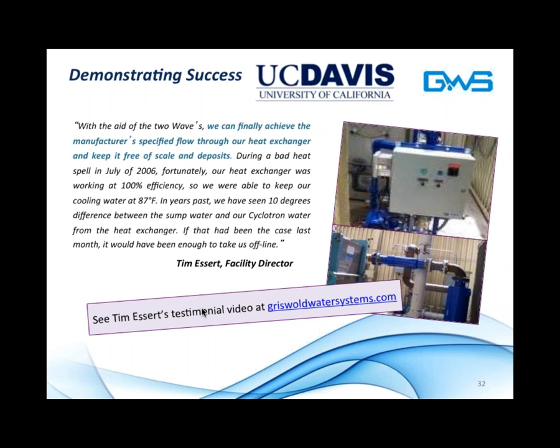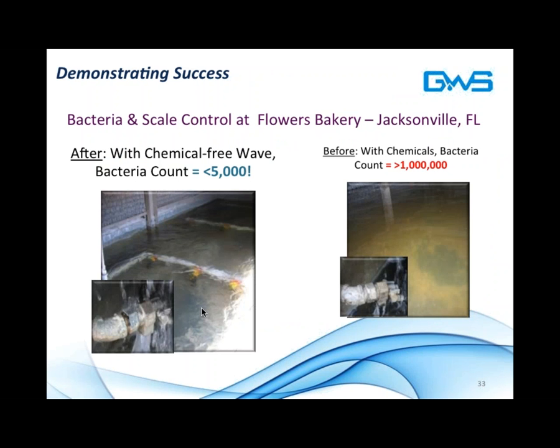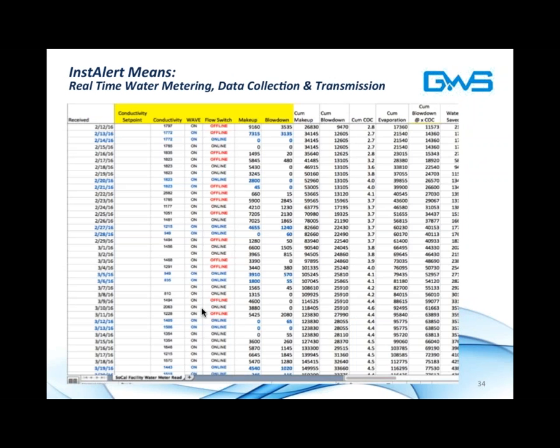They're very happy with that, and it's eliminated the scaling of their heat exchanger. Another job for us with very dramatic results on biological shows a bakery in Jacksonville, Florida, which was actually venting their kitchen exhaust fan, which included yeast, of course, into their cooling tower. The biological count for this system was over 1 million, and after approximately 4 weeks, you could see bacteria counts were less than 5,000 colony forming units per milliliter. The system is very effective.